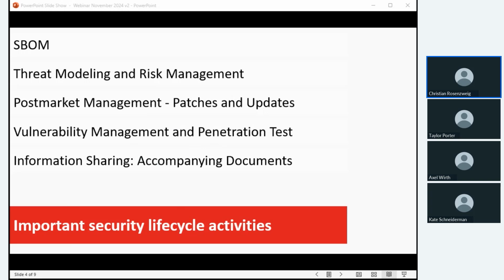This requirement can be skipped according to the postmarket guidance document if one of the following 4 conditions is met. So if you do not know of any serious events or deaths associated with the vulnerability, then you do not have to report it. Customers are informed within 30 days about the vulnerability and a remediation plan is created. The other condition is that within 60 days, the manufacturer fixes the vulnerability, validates the change, and distributes the deployable fix to its customers. And the last would be that the manufacturer is actively participating as a member of an ISAC or ISAO and shares vulnerability and threat information that impact the medical device. So under those conditions, you do not have to report uncontrolled risks to the FDA.